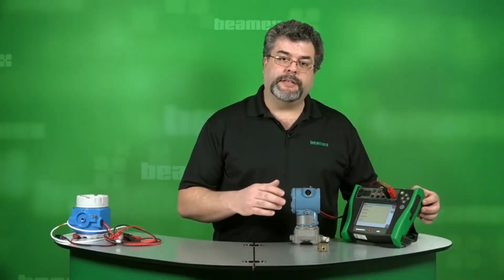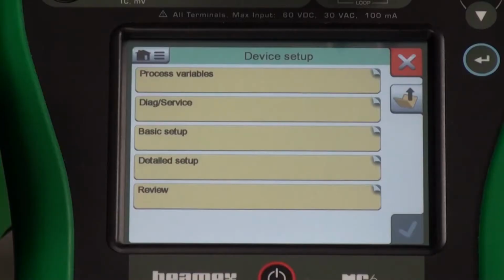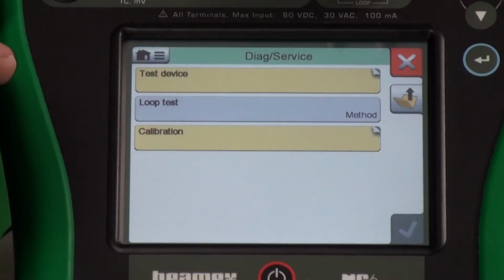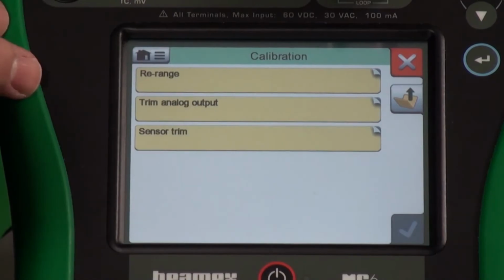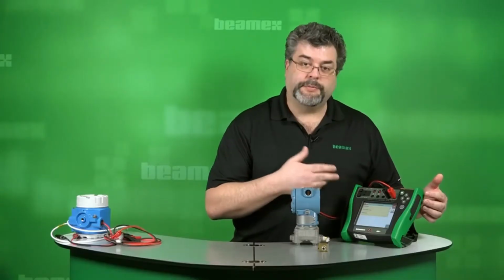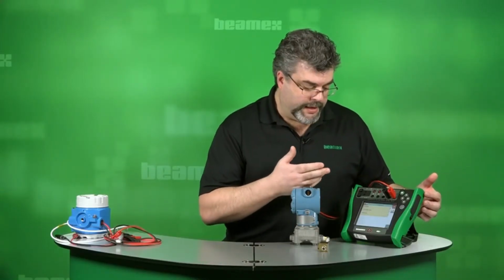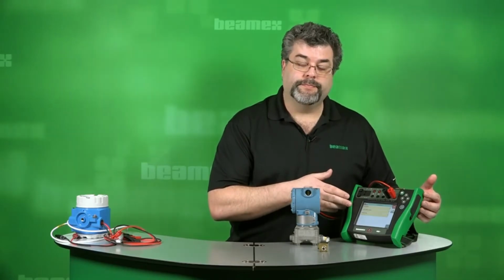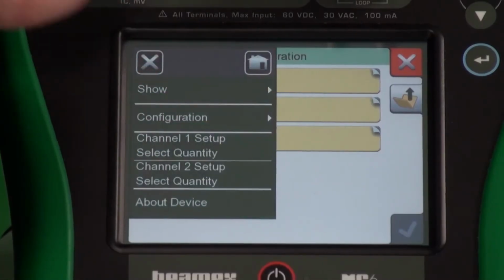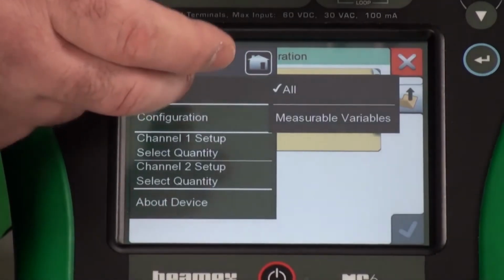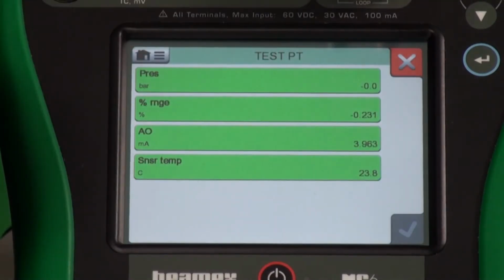On these type of devices, calibration, trimming functions tend to be under diag service. And then calibration. You have an option here for sensor trim and trimming the analog output. One thing that is easy to do is to find all the measurable variables with one option. Let me press the menu button. No matter where you are, you can press Show Measurable Variables. It'll bring up the measurable variables for this device.